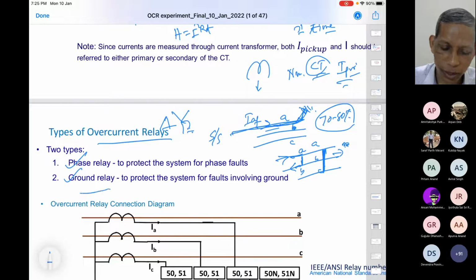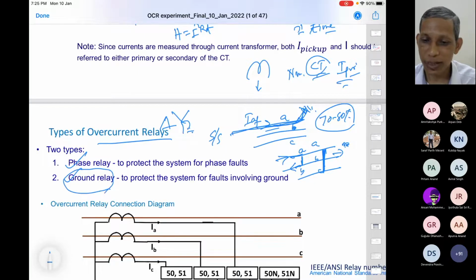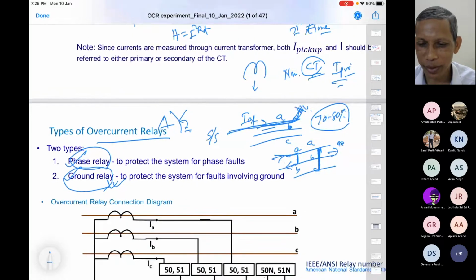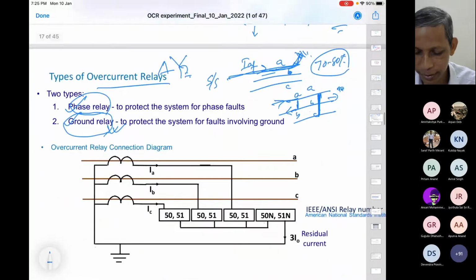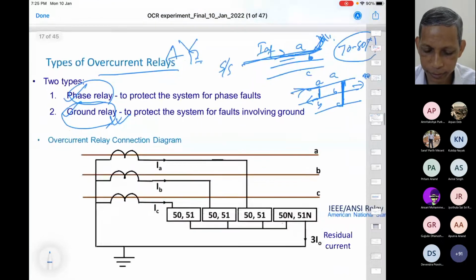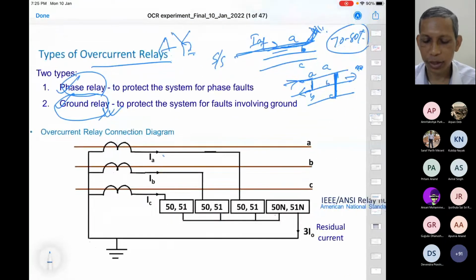We will see how to get the ground current and how to have the phase relays using the phase current. In phase relays, the fault is not involved with ground, but in ground relays, the fault is involved with ground. And we will see that ground relays are also more sensitive. You understand sensitive? Agree? The sensitivity is high in the case of a ground relay, so it can identify the fault better if the fault involves ground. We will see that. So the connection for these IA, IB, IC after the CT connection to the relays is like this.